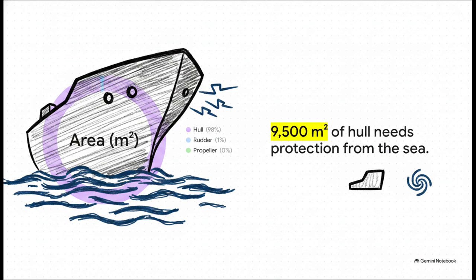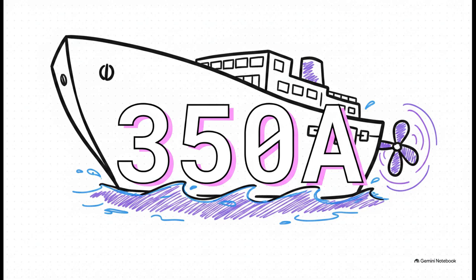Protecting 9,500 square meters of steel requires a serious electrical counteroffensive. To mount that counteroffensive, we need raw power, based on an applied current density of 30 milliamps per square meter for the hull and rudder, and a much higher 600 milliamps for the propeller. The engineering math tells us we strictly need 306.3 amps of continuous current.